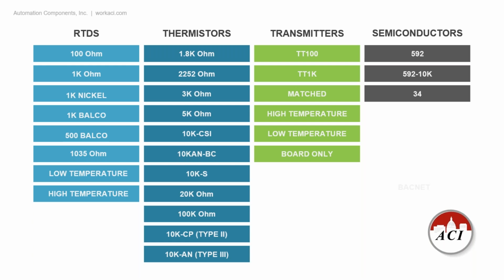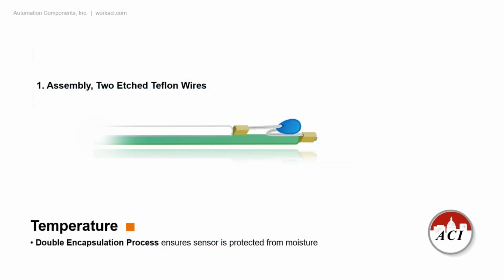Platinum RTDs are a linear curve. Thermistors are more of a bell curve, or non-linear, NTC, negative temperature coefficient. So as the temperature rises, the resistance goes down. The transmitters can only be paired with the RTDs, the 100 ohm and 1000 ohm on the top left there, which can be used in our transmitter boards. Just that question gets asked quite often as well.